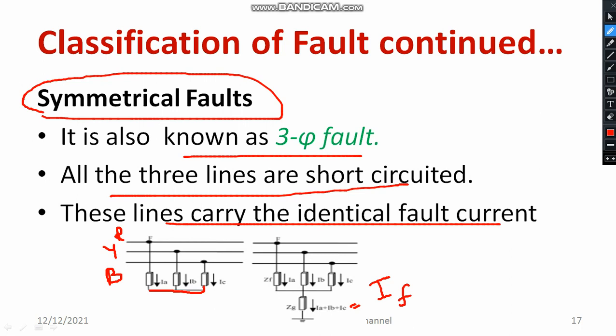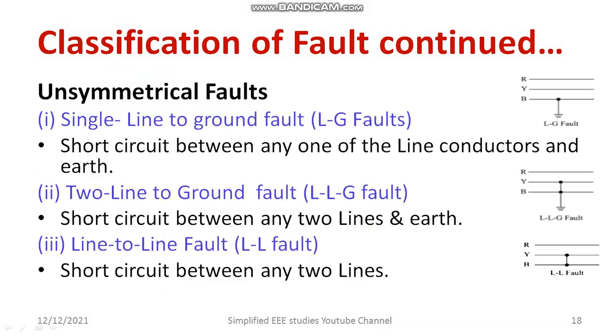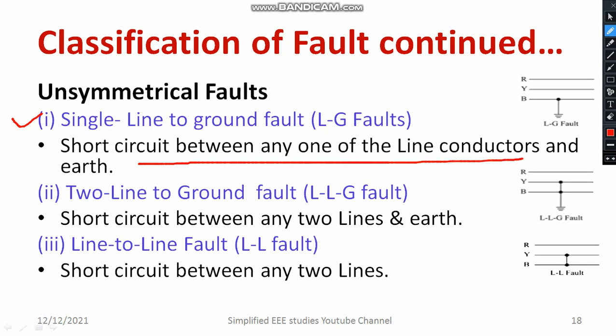Symmetrical fault is the most dangerous fault, but its occurrence is rare. Now let us discuss unsymmetrical fault. The first point is single line to ground fault, also known as LG fault or SLG fault. Here, one line is short circuited between any one line conductor and the ground — it may be Y and ground, or R and ground. These are generally known as single line to ground fault, and it is actually the most commonly occurring fault.